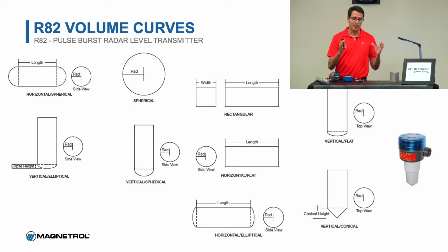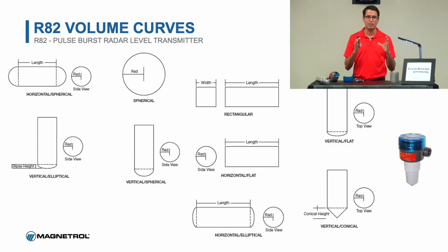Installation, again, it's very important. I'm not going to talk too much about this because whenever you order this particular device or whenever you're going to install this device, you always need the factory to know how you're going to install it, what's the size and geometry of your tank. Again, we can send a service guy out there, or our friends at TechStar can send a service guy out there. But we do need to know all these geometries of tanks, whether it's a cylinder or a bullet tank, where you are going to install the radar within the actual tank? Are there any obstructions? Are there ladders? Are there chains? Are there agitators? Are there stirrers, mixers, serpentines inside of the vessel?